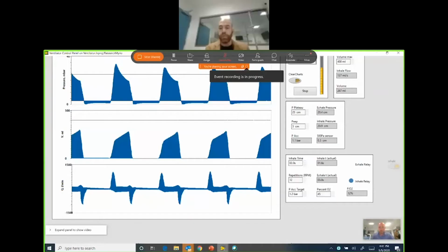This pressure relief valve would automatically open as soon as the pressure reaches 60 or 65 centimeters of water. The human being can normally withstand 80 to 100 in one shot, so it will not injure him, and that's very important. And all of these are actually the redundant part, because there are also the software safety features, since we are using redundant sensors: pressure and flow sensors on the inhale and pressure and flow sensors on the exhale.